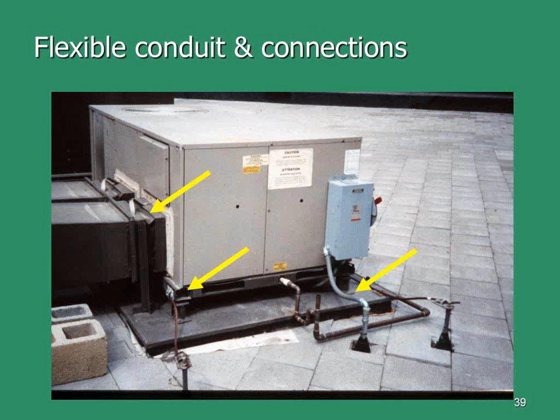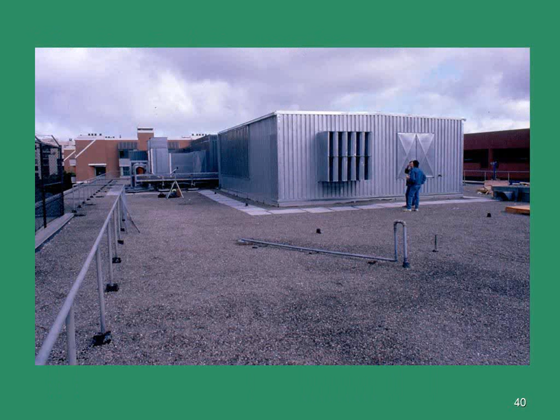Great questions. Now here's a case of just what you asked. We've got the fabric flex connector at the duct, and that's good, and we've got the vibration isolators here, but look what didn't get addressed. We've got flex conduit, we've got spring isolators, so this unit is fairly well isolated, but then we've got this natural gas or water line piping that comes in, and that's rigidly connected. So just like a 1% leak in an enclosure can hurt you a lot in terms of airborne sound isolation, 1 or 2 rigid connections can really mess up your vibration isolation package.